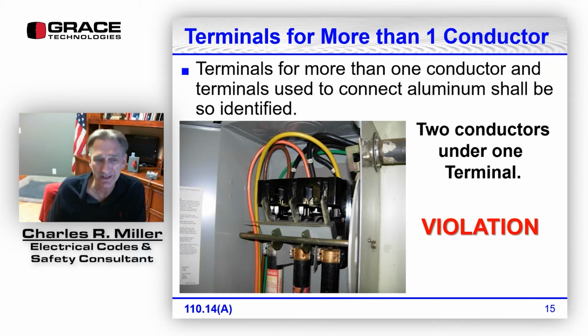And this illustration was an industrial plant I was at years and years ago. On the disconnect, you can see at the top it has two sets of conductors under one lug, a single lug, and that is a code violation. As a general rule, absolutely never put two conductors under one terminal. In some panelboards, they are listed so that it would be permitted to have two equipment grounding conductors of certain sizes under the same lug, but that's it. Neutrals or grounded conductors and hot or ungrounded conductors are never permitted under the same terminal.